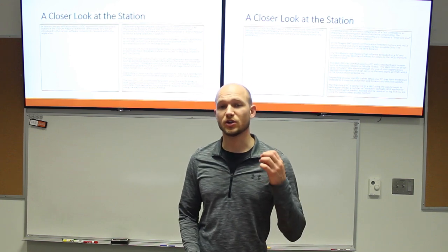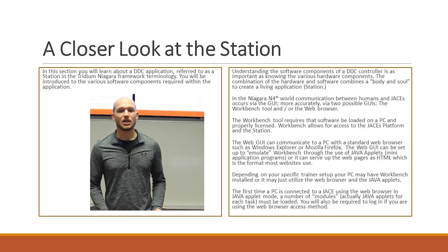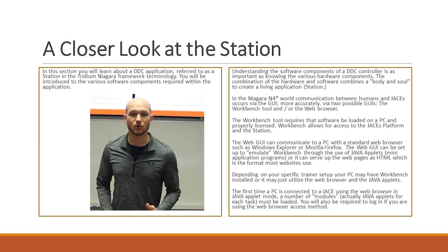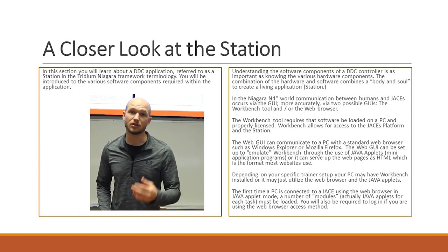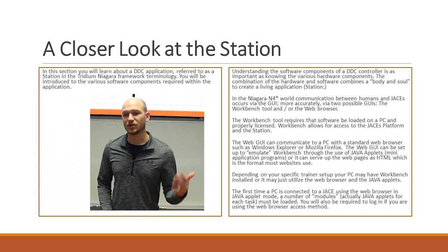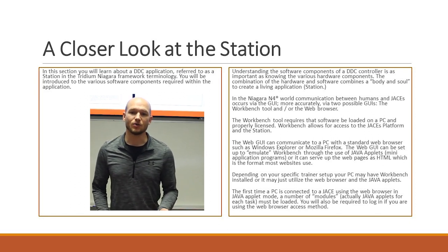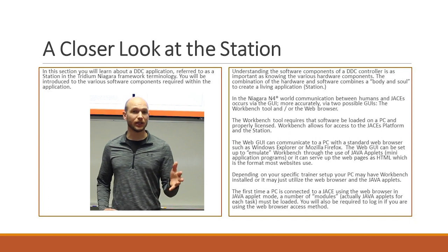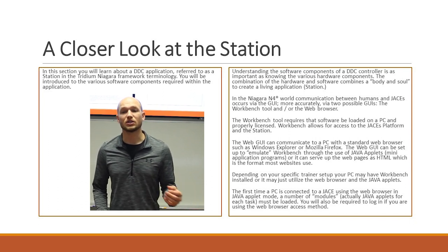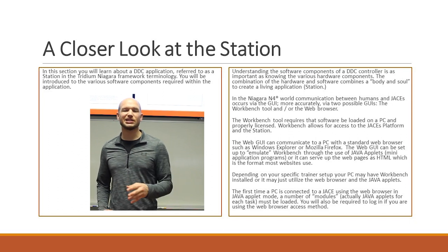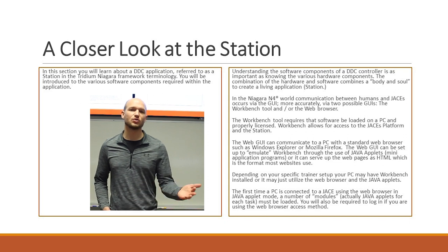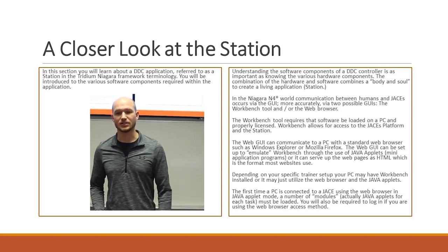Looking closer at the station — this is where you do unique programming for your client or facility. If you're using Workbench, that's the programming tool loaded onto a PC, and you'll need an annual license to utilize it. The other option is a web graphical user interface — the web GUI — which uses Java and is usually a bit slower. Most programmers in the field use Workbench, but they have the option to use either.